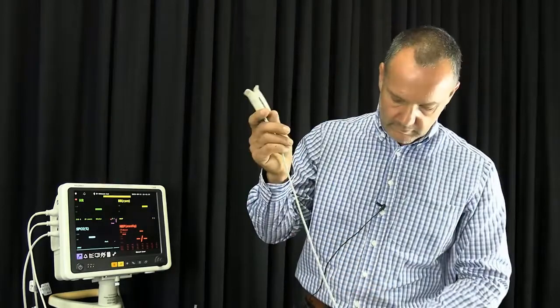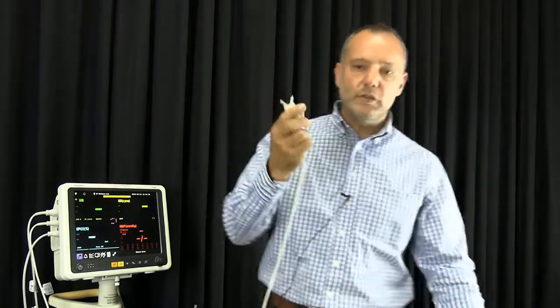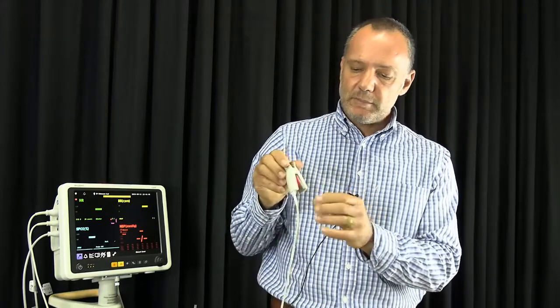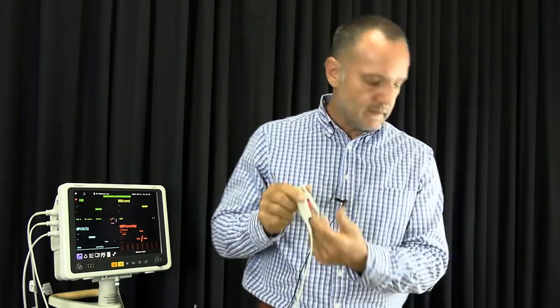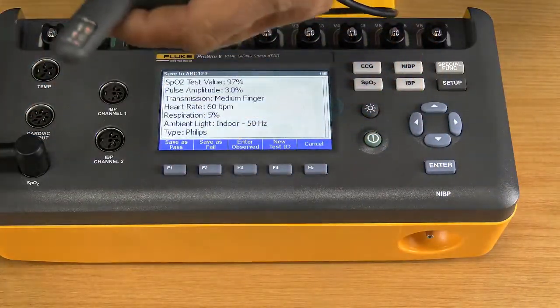And now I connect my SPO2 sensor. The important thing to remember with the SPO2 sensors is that some of them are those nice rubber ones which close off so you don't have any interference from light outside. But with these clip-ons, when it's on your finger, there's a lot of ambient light that can enter and interfere with your signal.